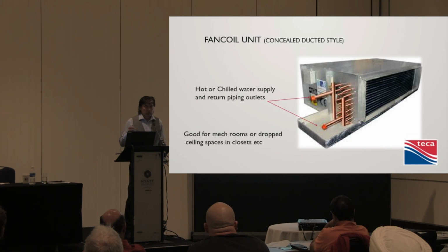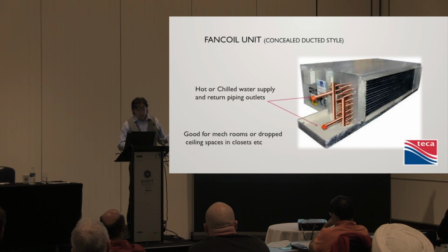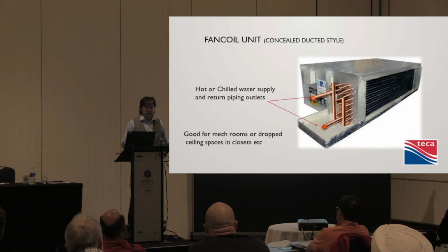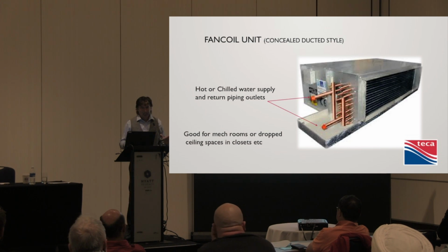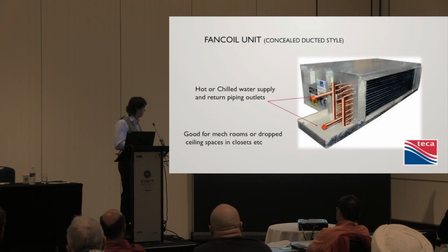So just to finish the makeup air thought, it takes power. There are two ways to do makeup air. You're bringing in outdoor air, so how are you going to heat that air? You can devote electricity to it. Some people put in electric furnaces. There are modulating electric specialized makeup air units. But when you talk 1000 CFM, that's like 7 kilowatts. That's a lot of power required for something that, I don't know, is it that important? If you already have a hydronic system, then why not consider using a fan coil for that?